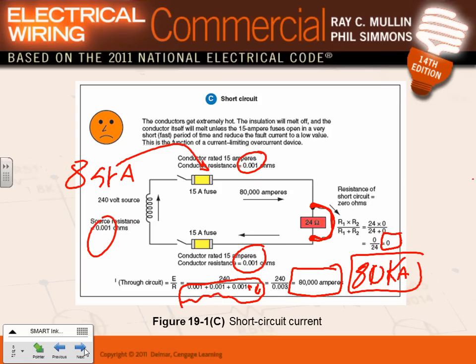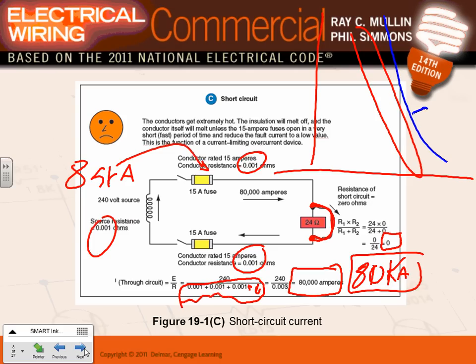So curve-wise, guys, this is how the curve looks. And the reason why I'm drawing the curves, not because I like to exercise my drafting skills, is because on Wednesday, that's what you guys are going to be seeing on the software. The software will be using graphs. So here's my fuse, sitting right in here, and my conductor damage curve. Remember that this is my number 14 conductor damage curve.